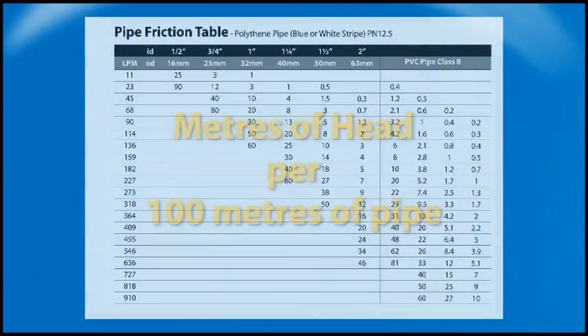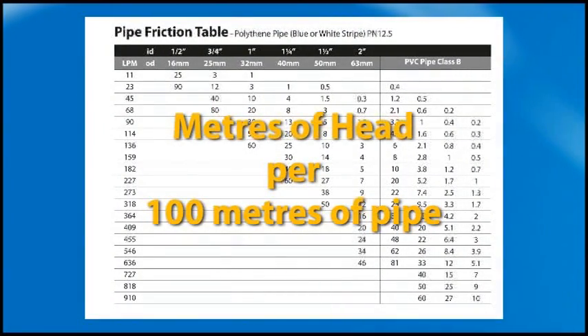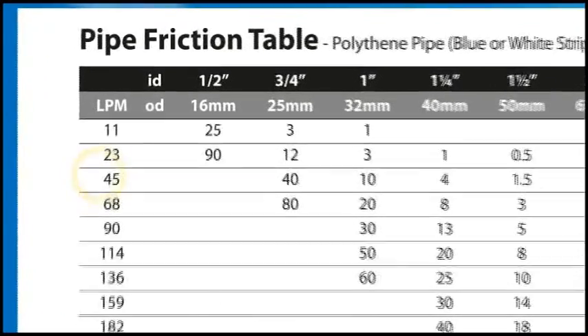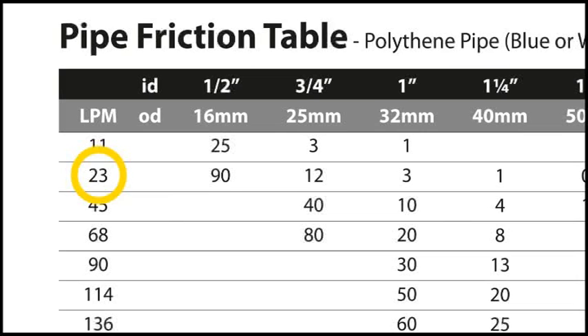A friction table is used to determine friction loss, expressed in metres of head per 100 metres of pipe length. This pipe friction table demonstrates how an increase in pipe diameter can reduce friction loss dramatically. If we select a flow rate of 23 litres per minute, and our pipe diameter is half-inch, the chart shows the friction loss would be 90 metres for each 100 metres of pipe.